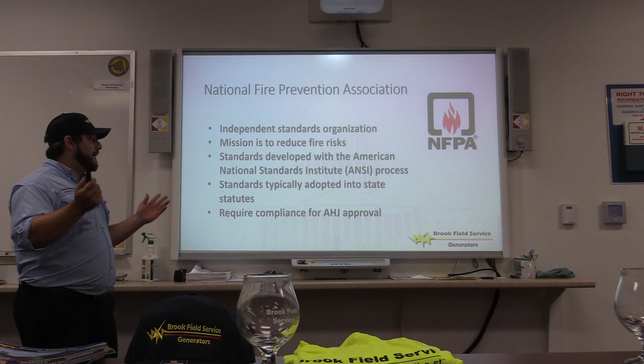The National Fire Prevention Association's most important code is NFPA 110, the standard for emergency and standby power systems. We're going to talk mostly about maintenance, but a little bit about installation standards and things to think about when investing in these systems. NFPA 110 pertains to emergency power sources, transfer equipment, controls, supervisory equipment, and all other equipment needed to supply electrical power to the load terminals of transfer equipment.